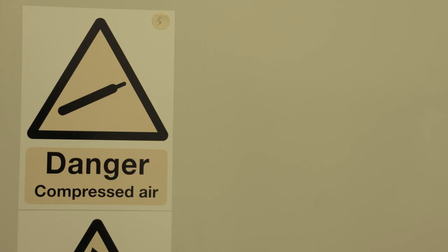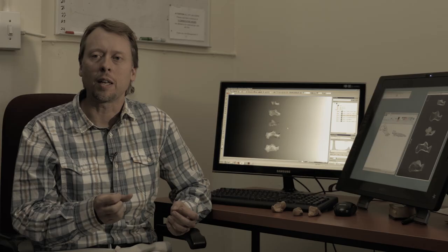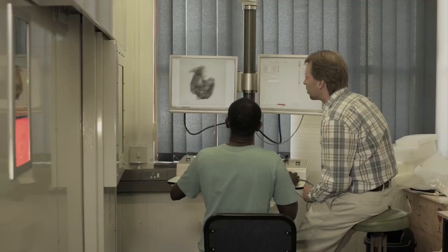The micro-CT scanner operates using x-rays and principles much like you would see in a hospital. We can image things down to three or four microns — that's .003 or .004 millimeters — so we can recover structural information from the tiniest of objects, whereas in a medical scanner you're usually limited to about one millimeter, or maybe .5 millimeters if you're lucky.